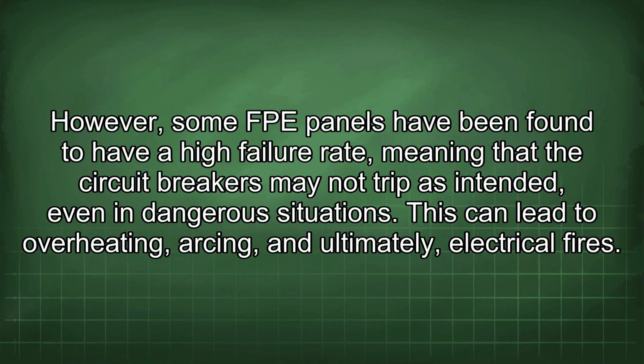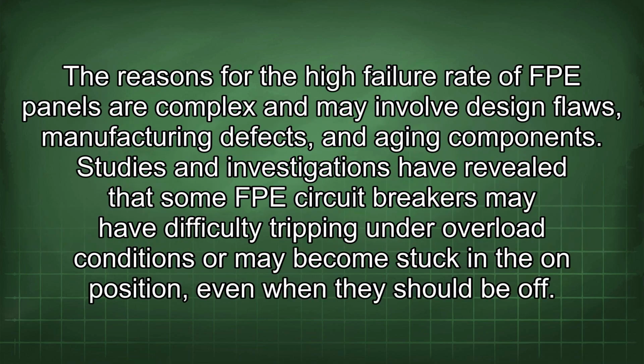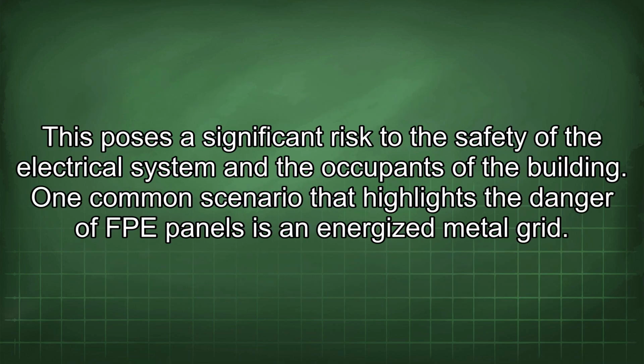However, some FPE panels have been found to have a high failure rate, meaning that the circuit breakers may not trip as intended, even in dangerous situations. This can lead to overheating, arcing, and ultimately, electrical fires. The reasons for the high failure rate of FPE panels are complex and may involve design flaws, manufacturing defects, and aging components. Studies and investigations have revealed that some FPE circuit breakers may have difficulty tripping under overload conditions or may become stuck in the on position, even when they should be off. This poses a significant risk to the safety of the electrical system and the occupants of the building.